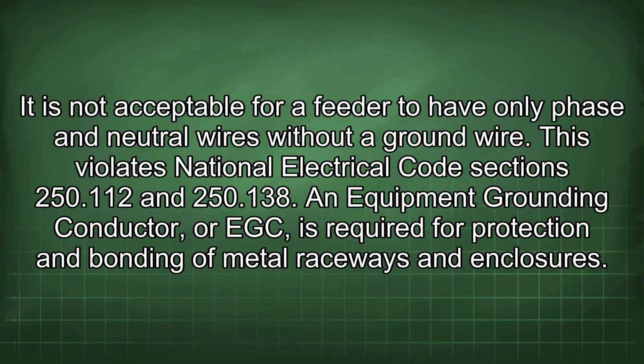It is not acceptable for a feeder to have only phase and neutral wires without a ground wire. This violates National Electrical Code sections 250.112 and 250.138. An equipment grounding conductor, or EGC, is required for protection and bonding of metal raceways and enclosures.